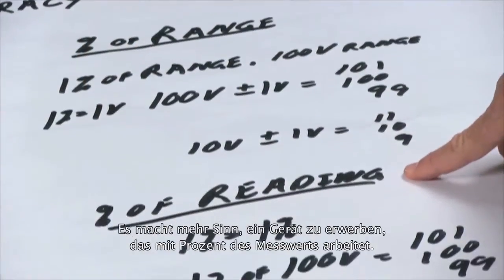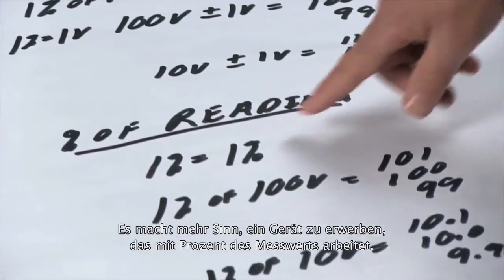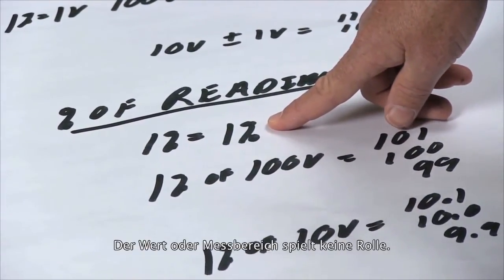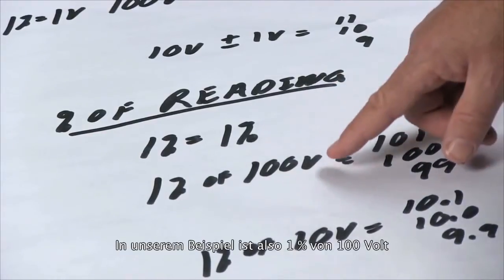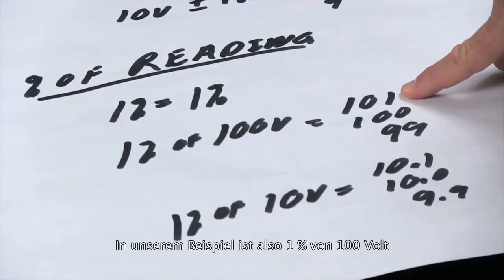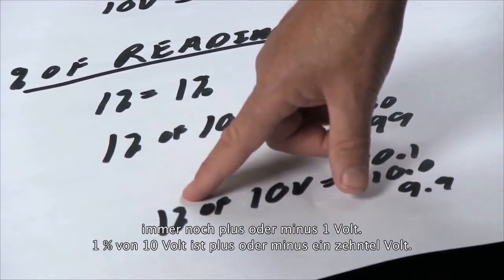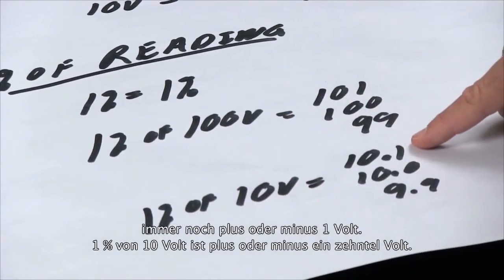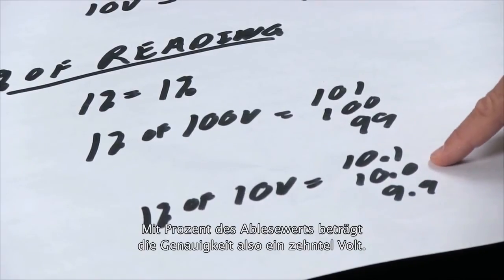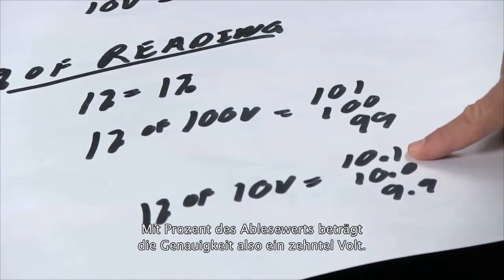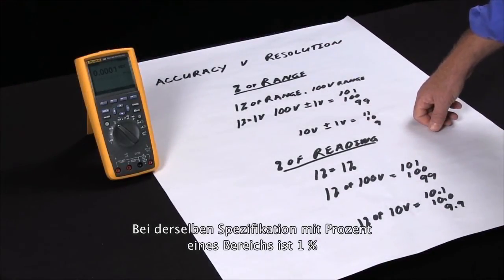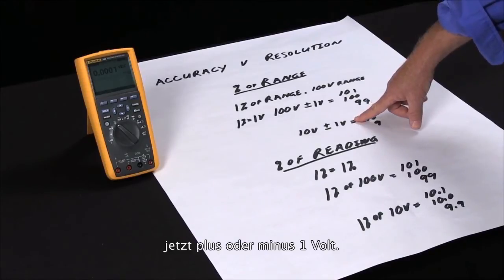A better way is to buy an instrument that has percent of reading — then one percent is one percent, regardless of what value or range you're on. One percent of a hundred volts is plus or minus one volt. One percent of ten volts is plus or minus a tenth of a volt. So with percent of reading the accuracy at ten volts is a tenth of a volt, whereas the same specification with percent of range gives plus or minus one volt.